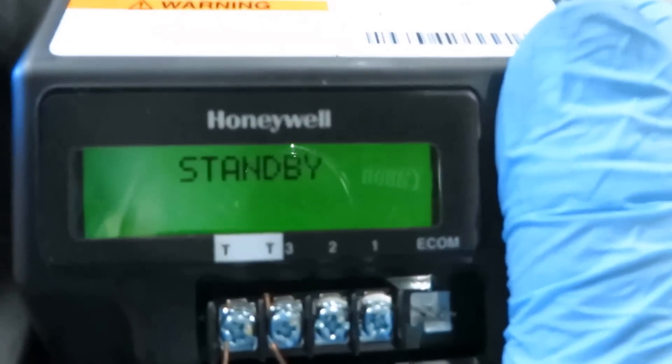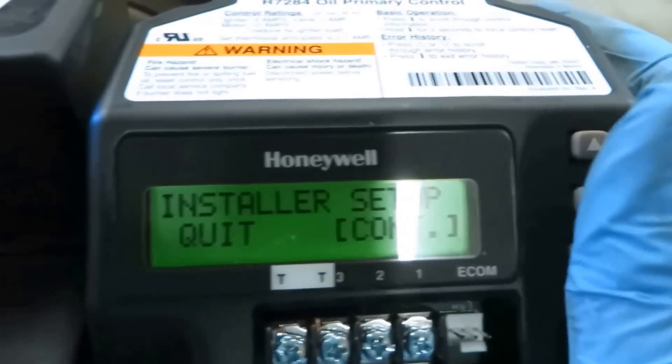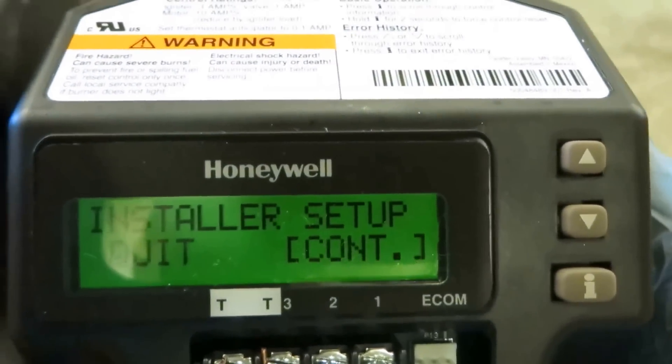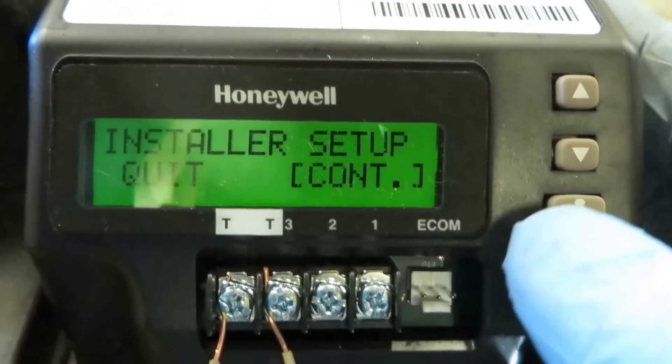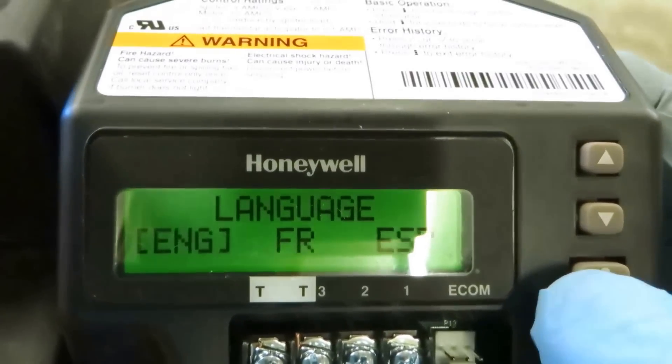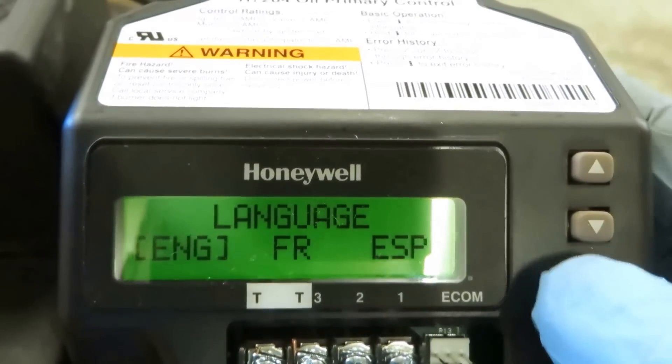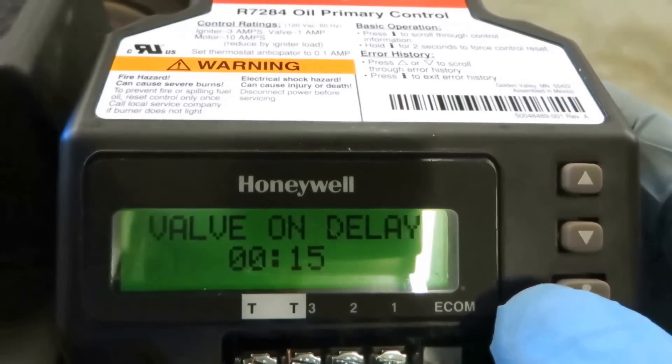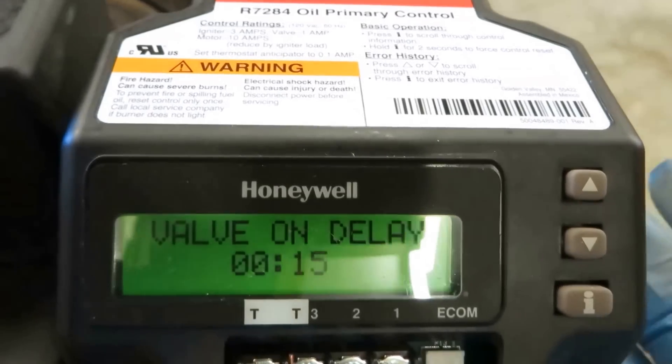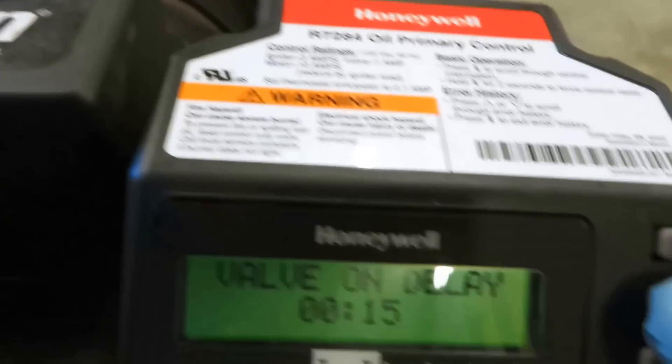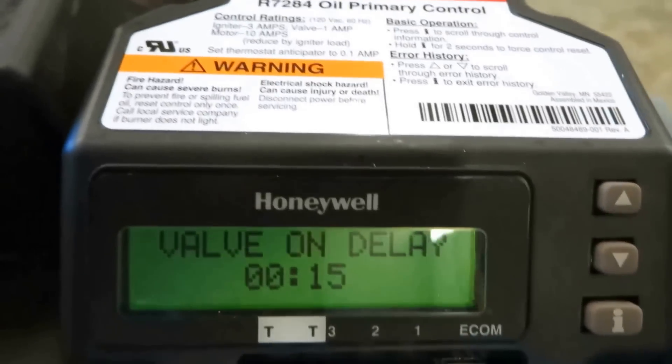Push all three buttons. Install, set up, continue. Hit this button here. English. The valve on delay, that's the delayed oil valve. You can set it for what you want. 15 seconds is fine with me.